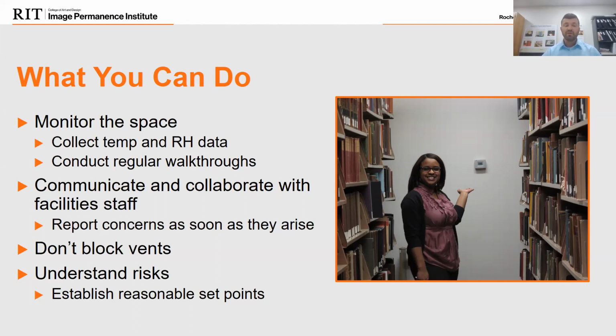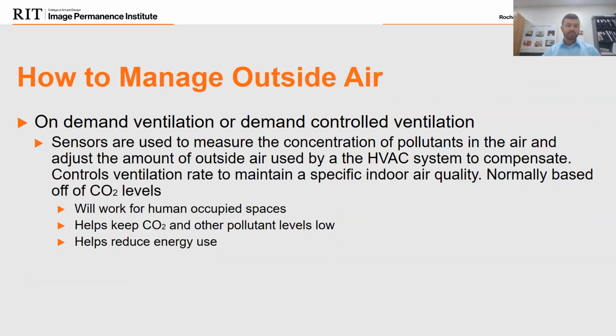And when it comes to understand your risks, one of the major things in there, establish a reasonable set point. We've been on projects, we've been called in, the collection staff, we've worked with facility, we've asked facilities, we want 65 degrees and 45% relative humidity in this space. We have to have that. And then when we talk to facilities, the first word out of facilities mouth is, yeah, we can't do that. We can't achieve that. The mechanical system was never designed to achieve that. So work with your facilities to come up with some reasonable set points. What can we realistically do?